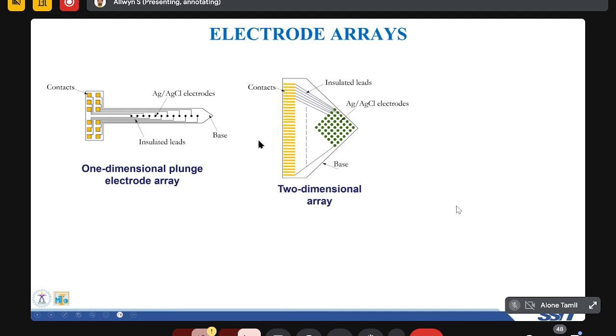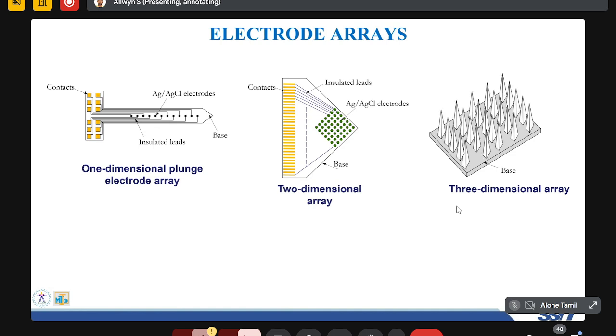In a two-dimensional array, it's a kind of flat grid of electrodes for surface mapping, used especially in EEG or cortical mapping, muscle activation patterns, or any spatial signal studies. Yeah, such kinds of electrodes are used. And finally, the three-dimensional array: same way, it's made of silicon microfabrication with a comb-like structure. This comb is around 1.5 mm, of varying dimensions, which can be chosen based on the application of the study. It's usually around 1.5 mm insulated tines, but only the tips are exposed, allowing high density neural and bioelectric signal recording.